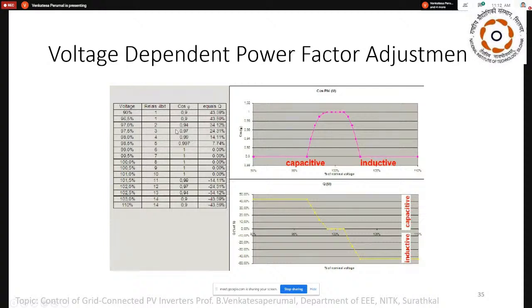The percentage of Q, if I talk about it, when the voltage is 90%, I'm supporting 43% of my reactive power requirement. If you look at it, the reactive power injected into the system is very, very high at 0.9 power factor itself.